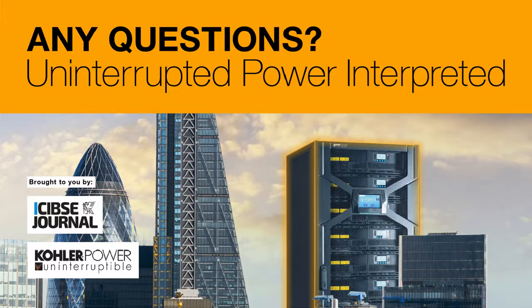There's some technical questions coming in. We've got a whole raft of questions here. It's a fairly technical question. What's the general performance abilities with regard to step loads applied to UPS? And are there any requirements regarding interfacing of standby generators and UPS units? So we've got two questions in that. Okay. Step load on UPSs can be 100%, no problem. And that can be single phase on one, on unbalanced single step of 100%.